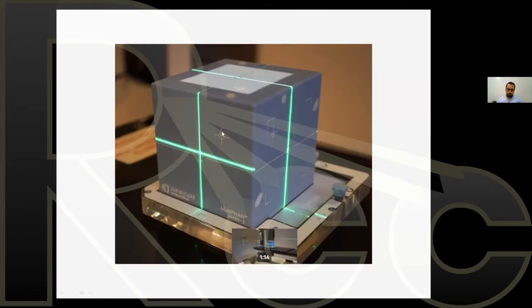A very important thing that these cubes have is a device, a phantom, an object that's embedded away from the central axis. And that is going to allow you to run your image guided testing. So very important with these phantoms. Not only do they check geometric accuracy, but they also give you the ability to target something that's off axis, shift the table using the software, and be sure that you're in the right place. I'll show you more about that.